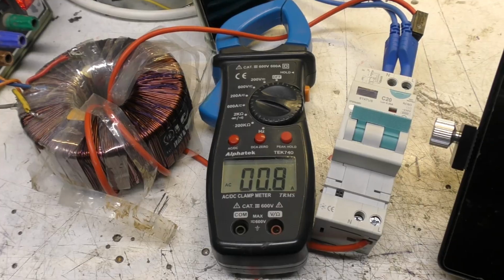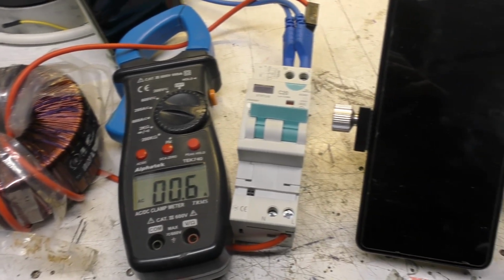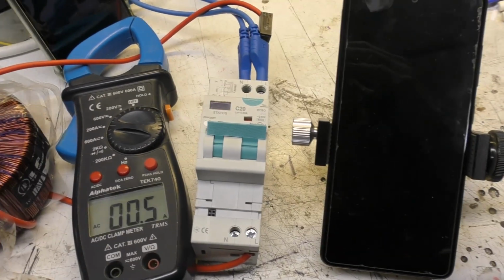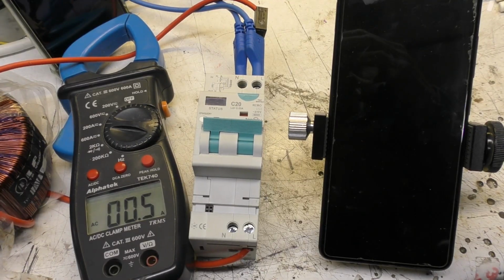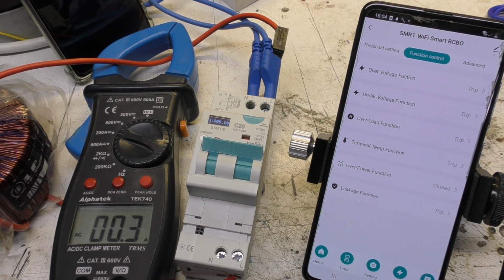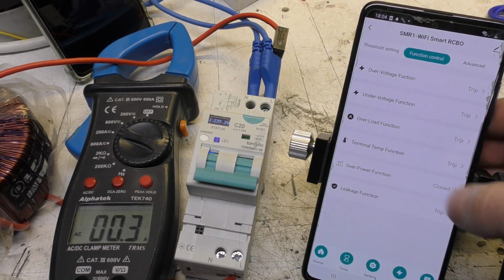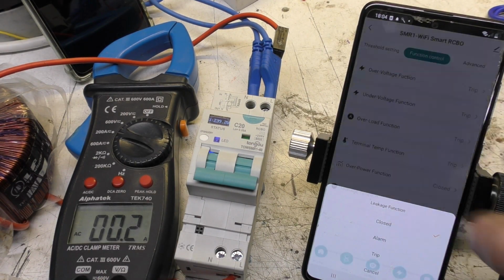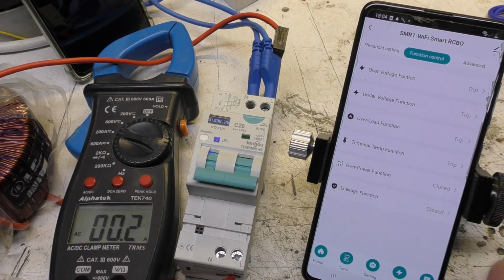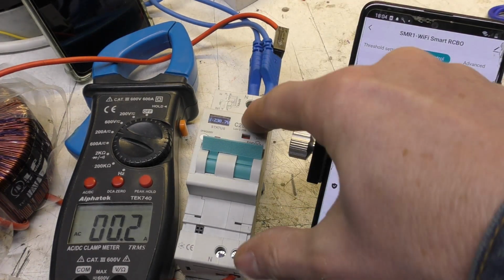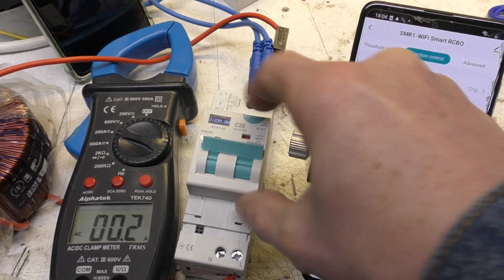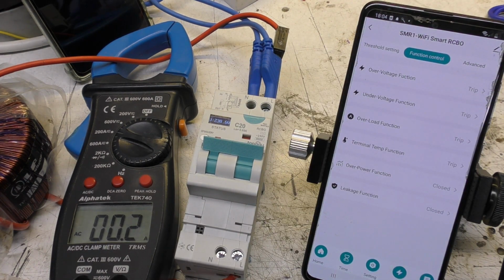Okay, to test the overcurrent, I've just got this simple setup: a variac into a toroidal transformer, a couple of turns secondary, which is injecting current between the live in and out, so it's injecting current into its current sensor, just so I can easily test high currents without having ridiculously high power dummy loads. Now doing this does trip the earth leakage function. But of course we can just go into the leakage function here and just turn it off. So we now have no earth leakage detection, even though the test button doesn't work. And we can now inject current in and see what happens.